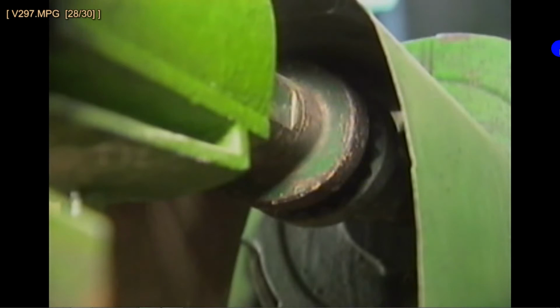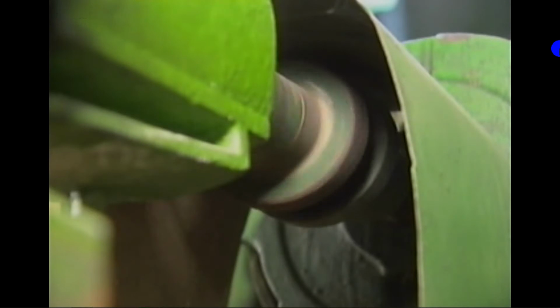In this part, we'll look at a reduced voltage start AC motor controller that can protect a motor against these current surges. Reduced voltage start motor controllers generally use resistors in series with the motors they control. The resistors increase the resistance in the motor circuit, which reduces the level of current during motor startup. After the motor is started, the resistors are bypassed, usually by means of an auxiliary circuit.